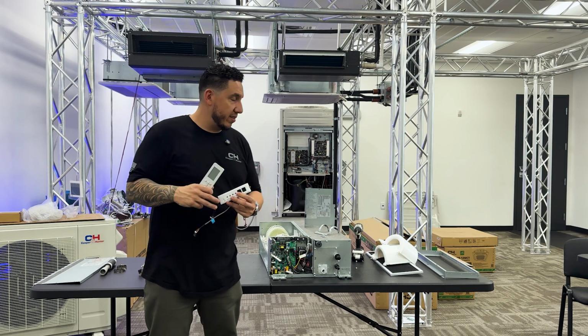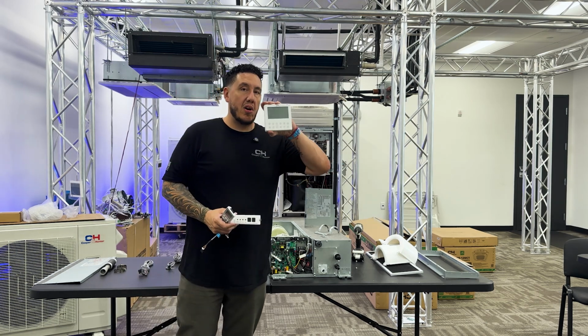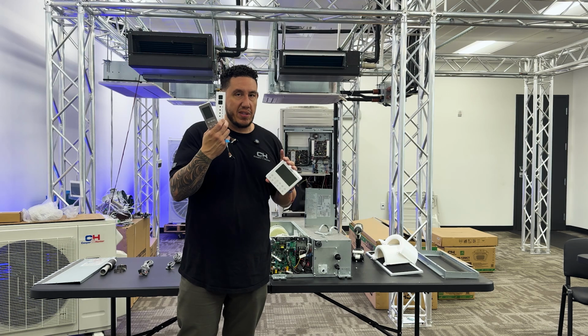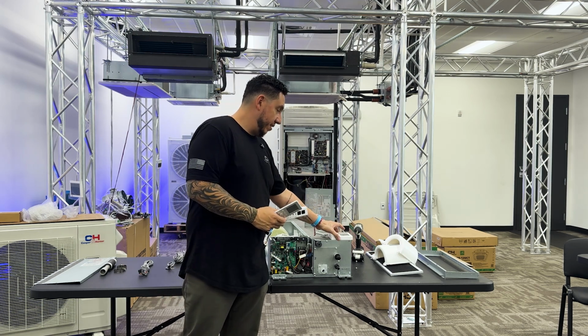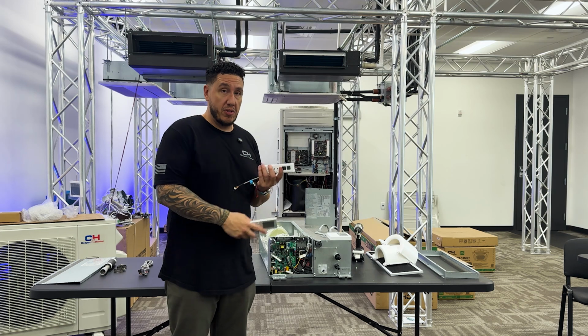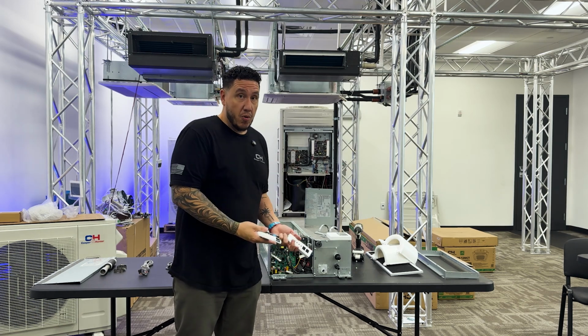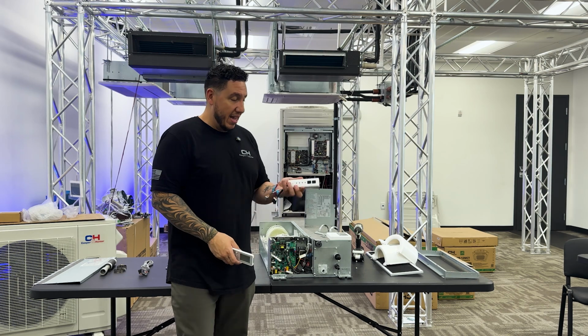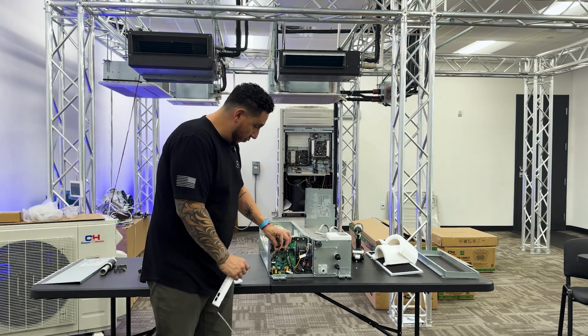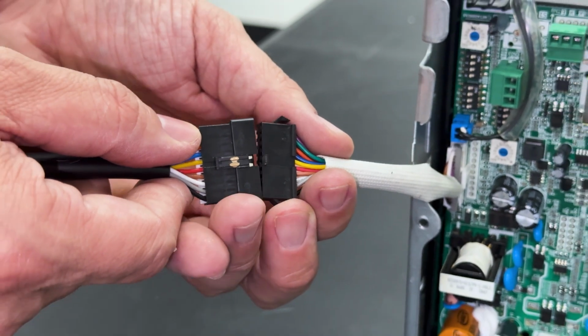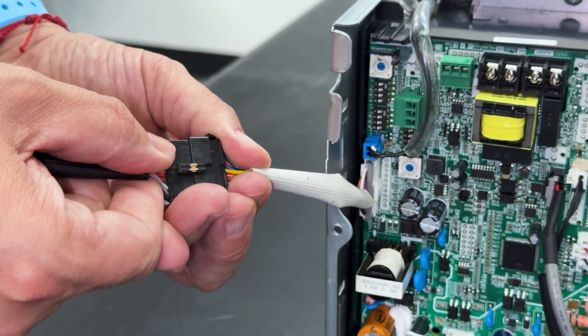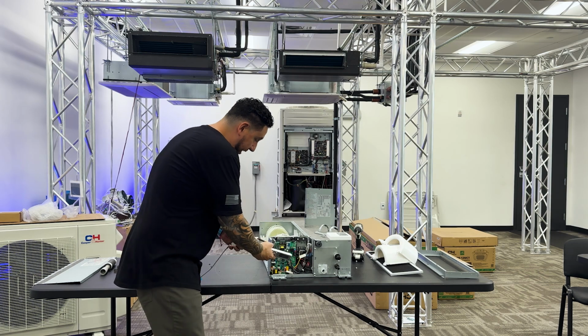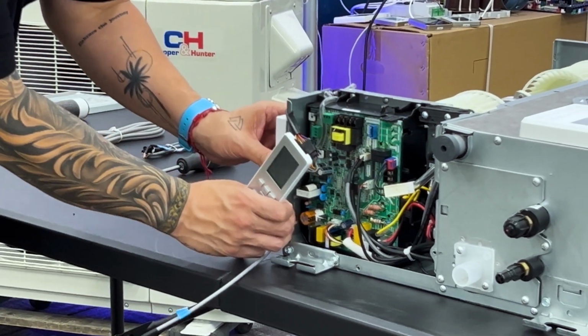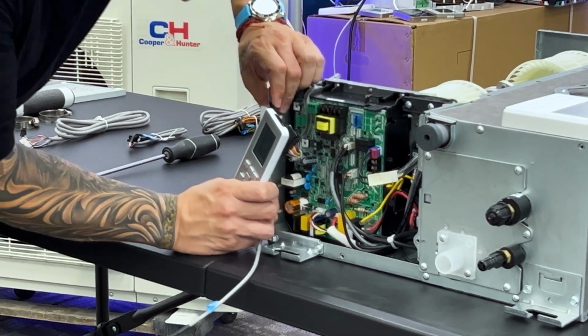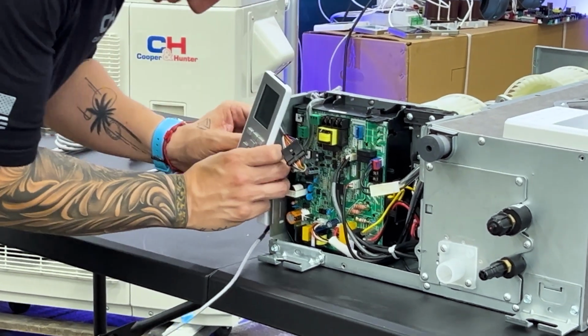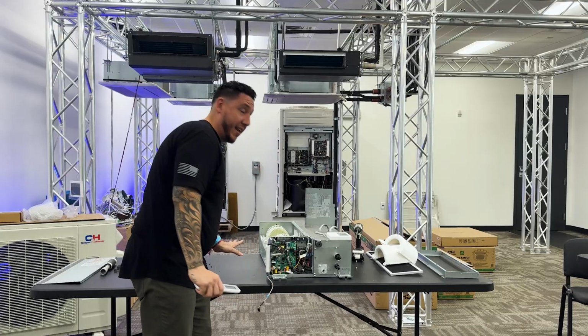Because if a technician is doing an installation, they decide, hey, I'm going to install a wall thermostat. I don't need the infrared receiver for a wireless remote. In most cases, that is correct. However, if they want to change the parameters of this unit and let's say have the blower wheel shut off when it reaches set temperature, they have to have this unit plugged in right here on this Molex cable connection so that they could enter engineering mode with the wireless remote. We educate technicians to just follow the notch that's here, and you could clip this right onto the bracket that comes pre-installed, so that way you could set it and forget it.